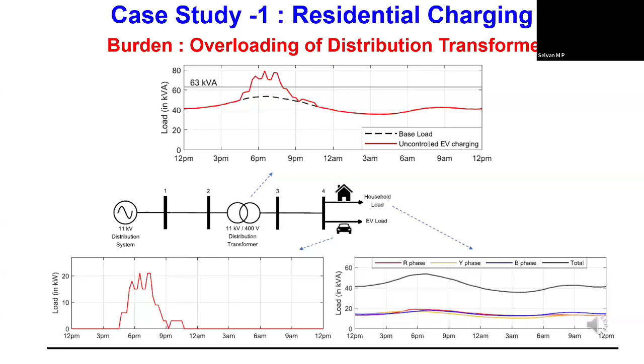Since it is a simulation, we could see overloading. Practically, if I overload the transformer, there may be a possibility for interruption of power due to the fuse. If the fuse is able to withstand this overload, sustained overloading of the transformer may lead to reduction in its lifetime. So this should not be allowed. Somehow I need to manage this and go to coordinated charging. So this is one problem in the distribution transformer.